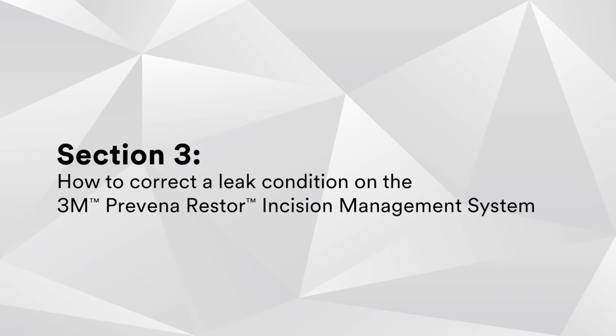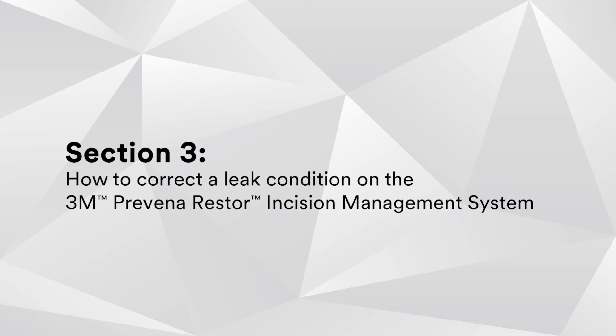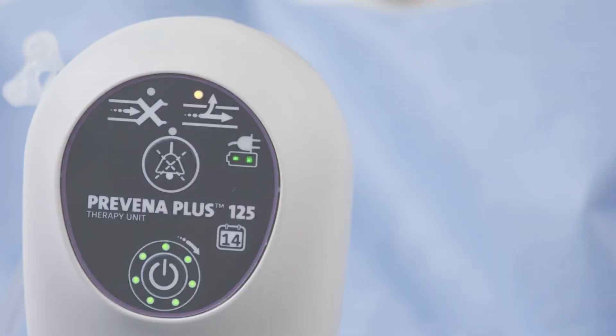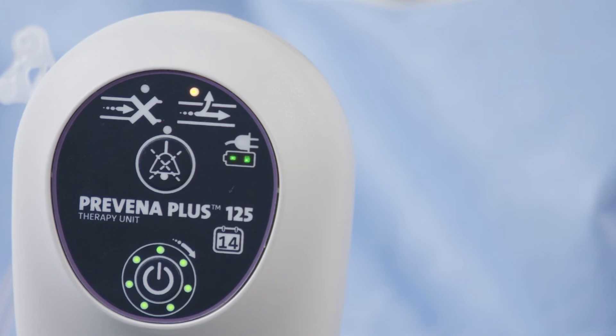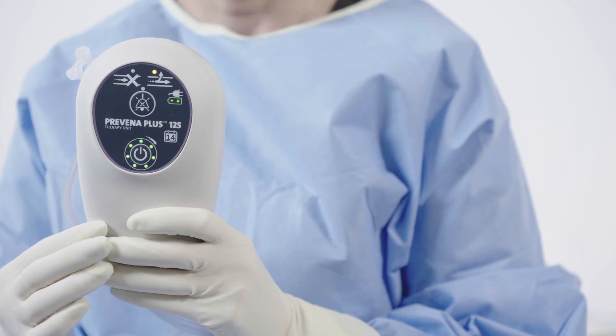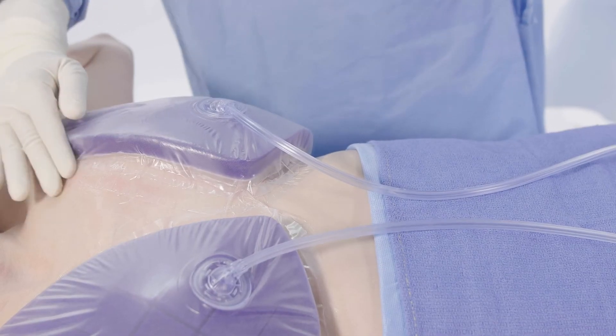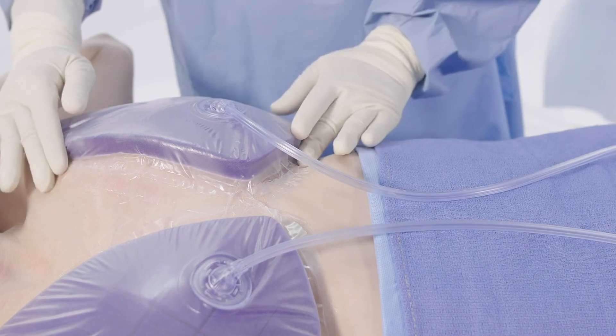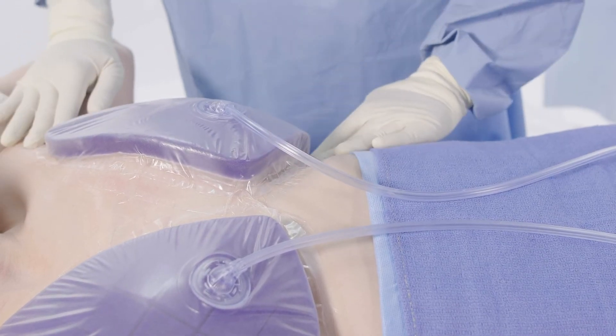Let's now move to our final section: how to correct a leak condition on the Prevena Restor incision management system. If there is a leak around the dressing, a solid yellow LED will turn on above the leak symbol on the device. The leak alert will sound two beeps, repeating every 15 seconds. To correct a leak and create an adequate seal, follow these steps.